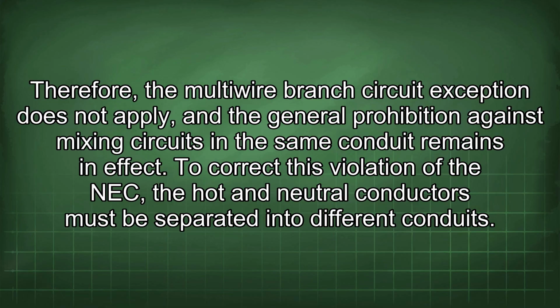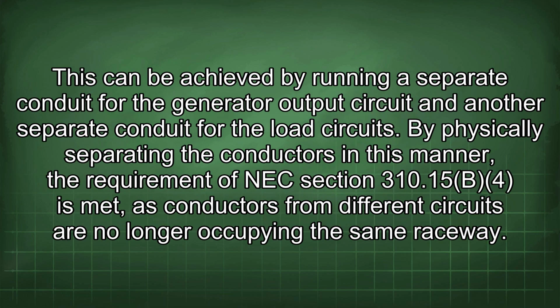To correct this violation of the NEC, the hot and neutral conductors must be separated into different conduits. This can be achieved by running a separate conduit for the generator output circuit and another separate conduit for the load circuits. By physically separating the conductors in this manner, the requirement of NEC Section 310.15(B)(4) is met, as conductors from different circuits are no longer occupying the same raceway.